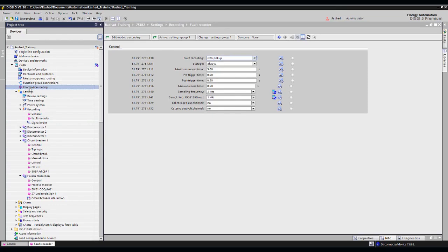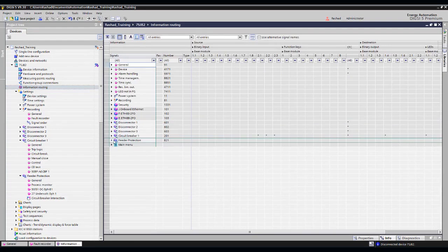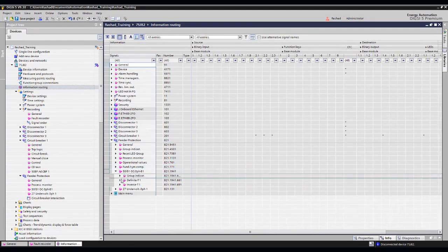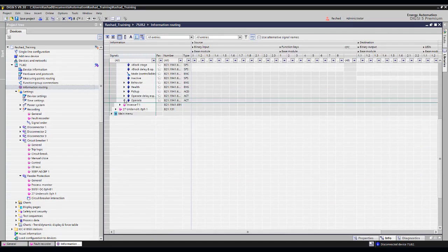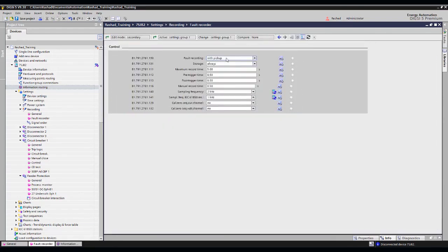Consequently, if you want to record anything you want, let's assume, for example, you want to record on a specific phase. You will go here, open, for example, whatever you have, and come to the pickup or whatever it is. And come here to your device, and here's the recorder. You press record and tell it X, meaning routed, which means this will be recorded only. But if you notice here that I told it, no, I don't want it with any pickup for any function. I want it user defined, meaning I choose.